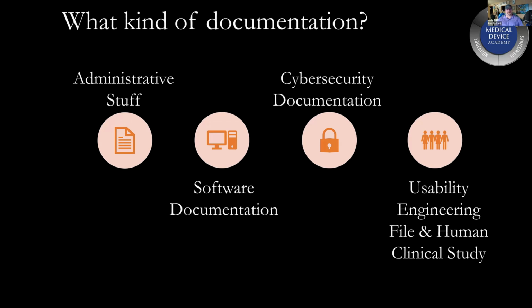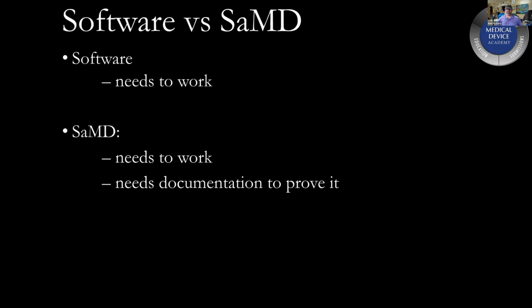I don't even have to claim compliance with 62304. The FDA actually has a place for it in the software documentation section. It's either the fifth or sixth requirement for an attachment, and I can show you where that is. Here's a screen capture of it. Attachment number 7: you have two choices. You either attach a certification statement saying you comply with 62304, or you attach all your procedures explaining how you meet all the requirements that are in 62304.